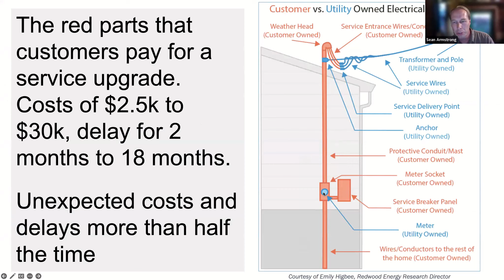The simplest thing you could do is get a connector, also called a meter collar. This is the meter itself. Going back to the first image, you own everything that's red; they own the meter and the wires, but you can put a meter collar behind that blue circle. With this meter collar, you can plug in not a 4 kilowatt array, but up to a 15 kilowatt array.